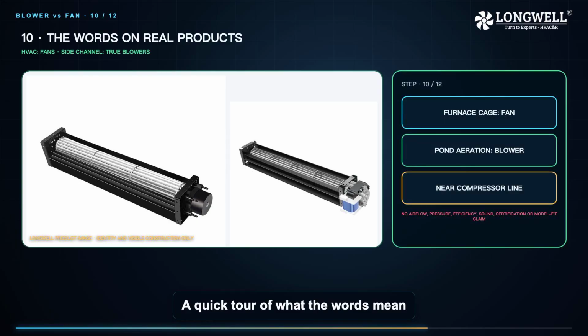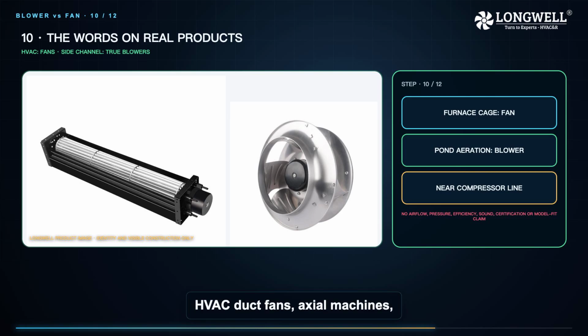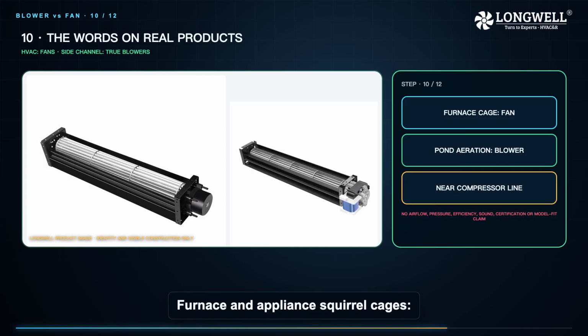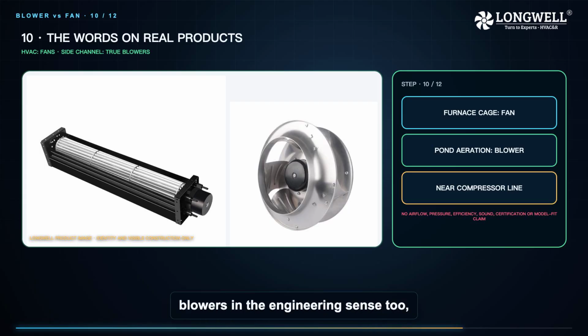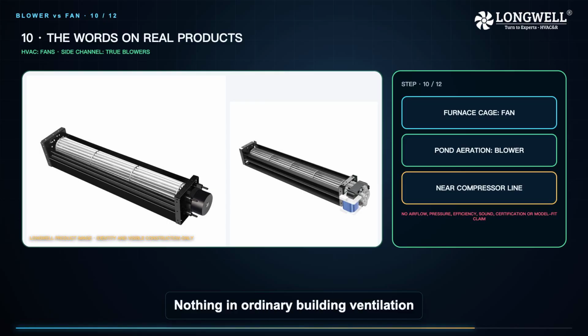A quick tour of what the words mean on real products. HVAC duct fans, axial machines, plug fans, fan walls, fans, whatever anyone calls them. Furnace and appliance squirrel cages, blowers by custom, fans by ratio. Pneumatic conveying, pond aeration, vacuum applications, side-channel machines, blowers in the engineering sense too, often flirting with the compressor boundary. Nothing in ordinary building ventilation genuinely needs the compressibility mathematics.